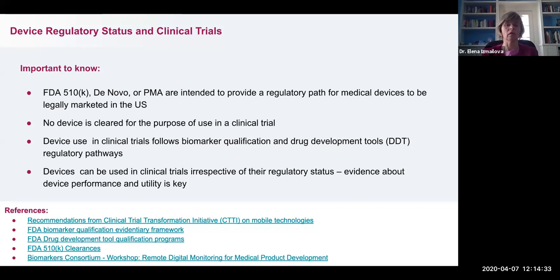Devices that have 510(k) clearance, 510(k) de novo status, or PMA pre-market approval are intended to provide a regulatory path for medical devices to be legally marketed in the US. Device manufacturers have to comply with certain laws, and these paths are designated to ensure that happens. No device is cleared for the specific purpose of use in clinical trials.